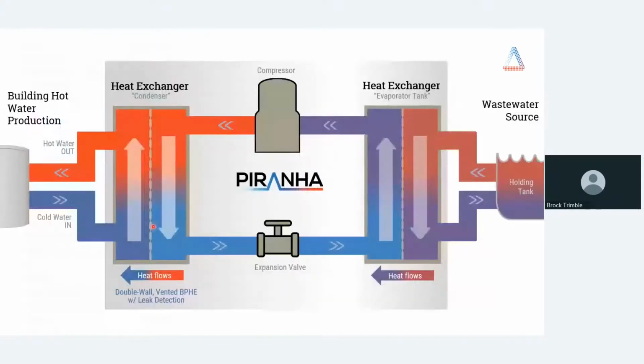Okay, now a little bit of a science lesson for everyone who's unfamiliar with heat pump technology. The Piranha, as I mentioned, is a heat pump, and heat pumps have been around for 100 years. We've done very little to change what a heat pump is, other than to develop a way to draw energy from wastewater. Now, the problem with wastewater is that there are solids. Anything that you might flush down the toilet, that might drain down a tub or through a kitchen sink, that type of thing, will make its way into the wastewater. Those solids would typically have an effect on any other type of heat exchanger, clog it, and eventually degrade flow. They wouldn't be able to transfer energy effectively.